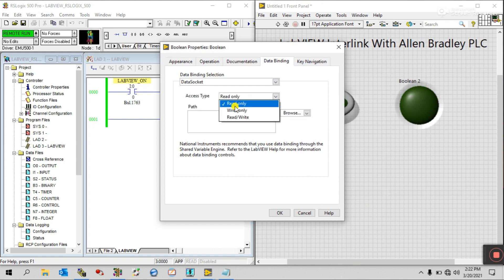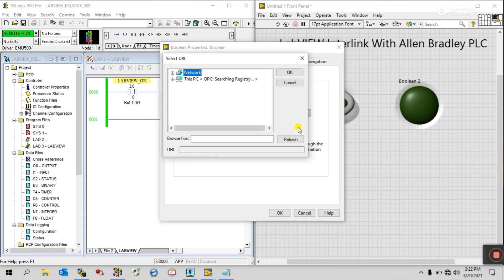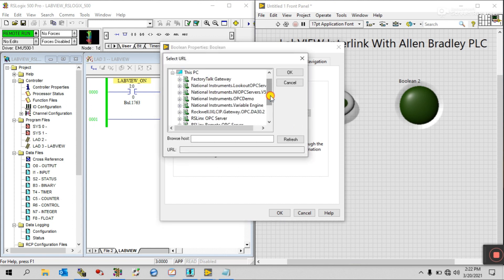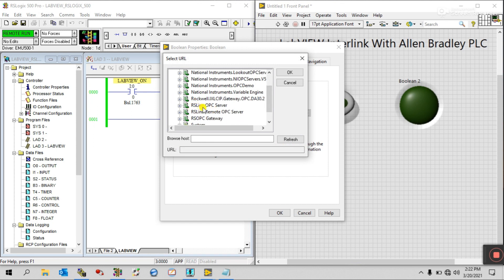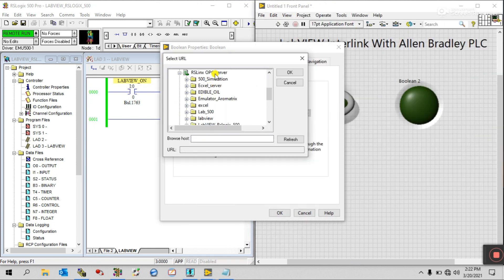Choose Read and Write as needed, then click Browse. You can see various options — select DSTP and open it. After a few seconds it will open, and you can see if your PLC has an OPC server it will show here. This is RS Linx OPC Server — that is the Allen Bradley software name. If you are using another PLC it will have a different name.